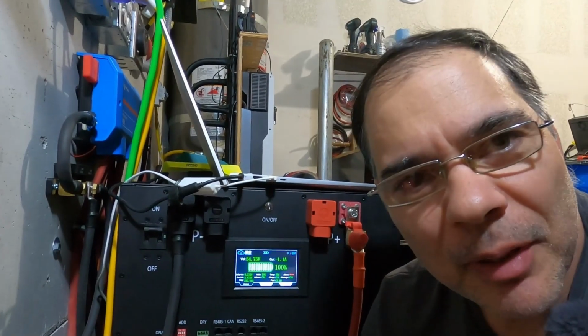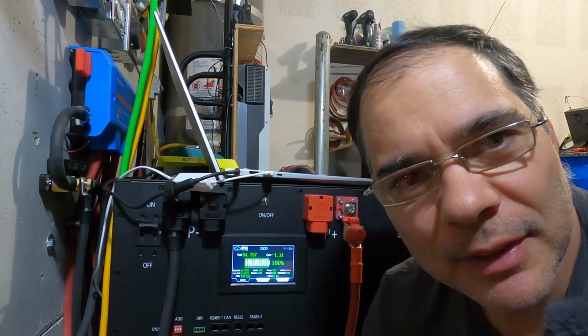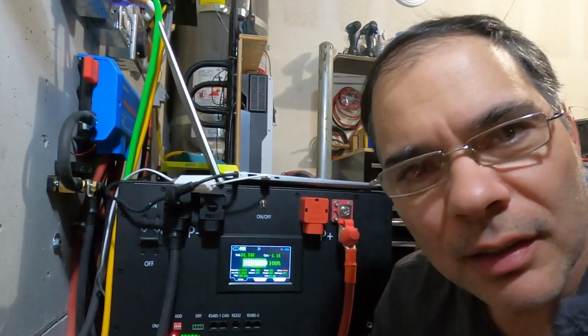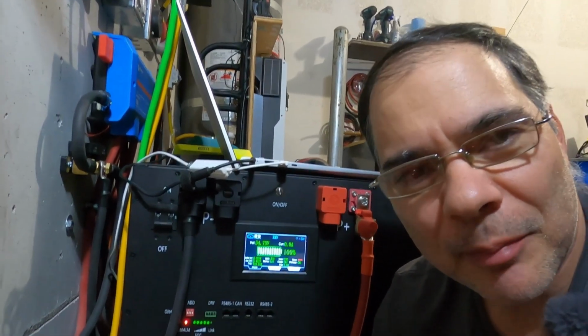Okay, we're going to disconnect this from the charger and let the BMS get the deviation down to about 50 millivolts or so, and then we'll connect up the charger and then charge it the rest of the way. So the nice thing about this battery, all I have to do to disconnect it from the system is flip the breaker. Now we can let the BMS do its dirty work. Remember, when we built the battery, we did nothing to the cells. We did not capacity test them in any way. We just took them out of the cell boxes, threw them in the case, and built the battery. This is a test to see how well the JK BMS can handle the job.